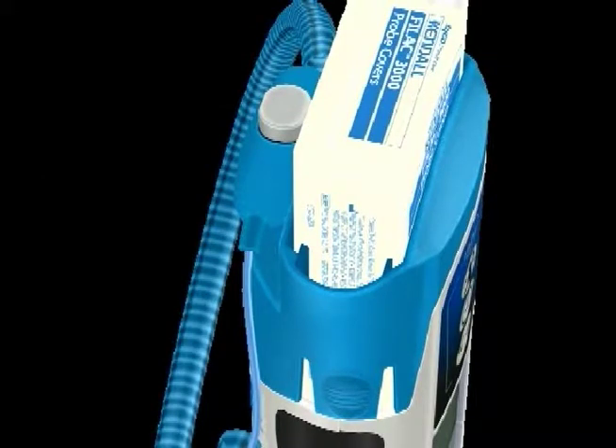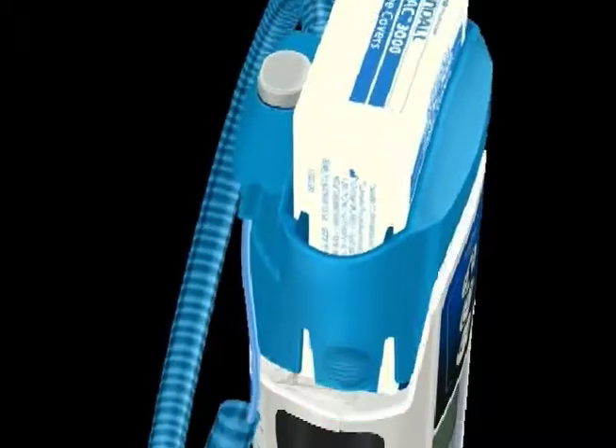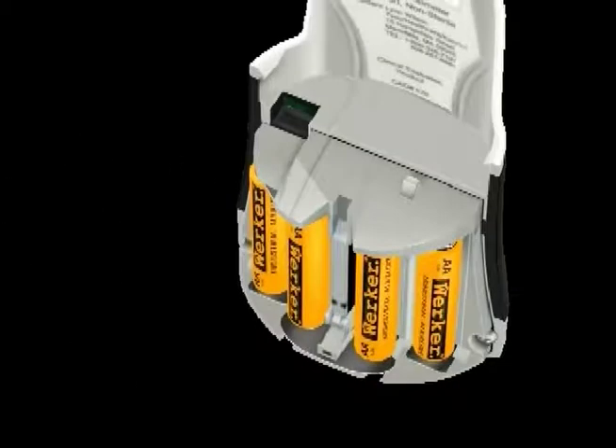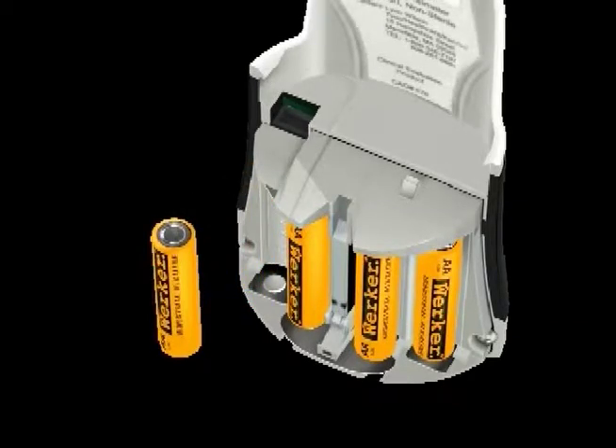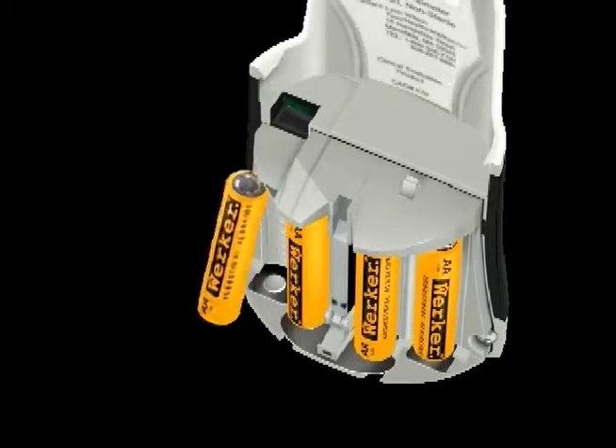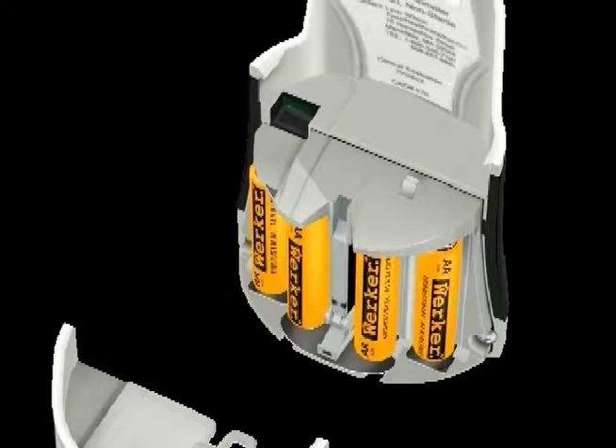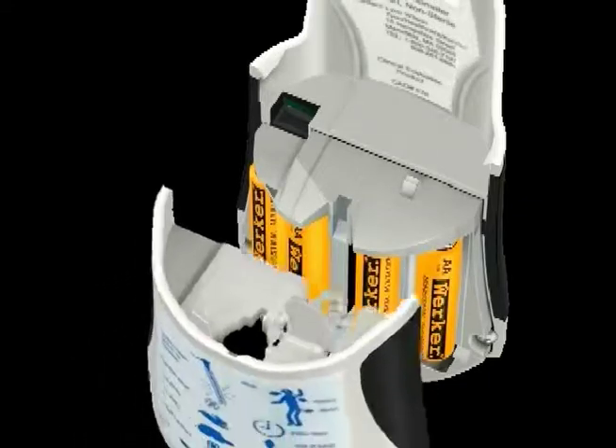The Filac Advanced Electronic Thermometer operates using four standard disposable AA batteries. When the low battery indicator icon is displayed, you should immediately change the batteries as the thermometer has approximately 50 temperature readings remaining. New alkaline batteries will last approximately 12 months, with a lithium battery lasting approximately 2 years during normal operation. See the operator's manual for complete instructions on how to change the batteries.